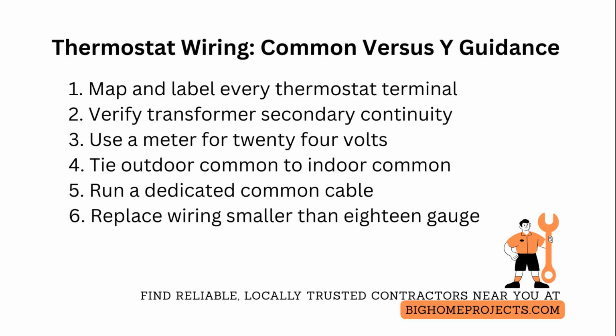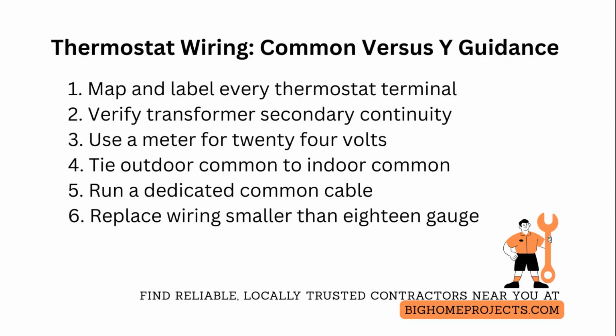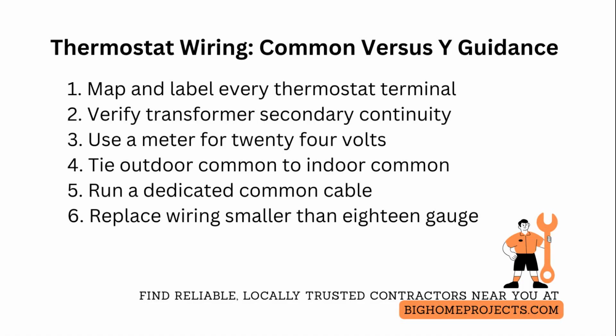When simplifying installation to reduce polarity errors, run a dedicated common from the transformer to the thermostat location rather than relying on the Y conductor as a return path. This avoids inadvertent swapping during future swaps.